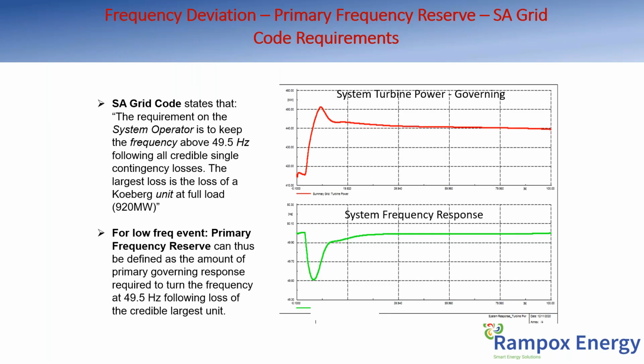If we look at what the Grid Code states in terms of primary frequency response, the Grid Code for South Africa says the requirement on the system operator is to keep the frequency above 49.5 hertz following all credible single contingency losses. The largest loss being the loss of a generation unit, that was 920, I think now it's 950 — my Eskom colleagues will correct me — but that is still the single largest contingency that the system operator needs to operate to.